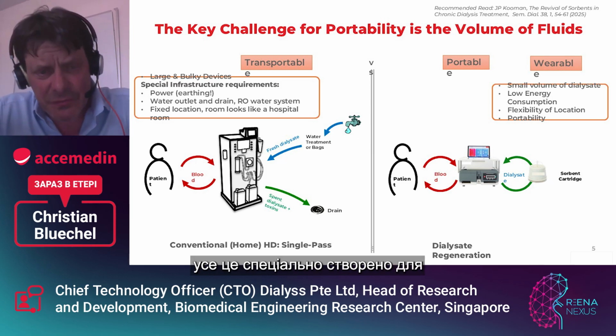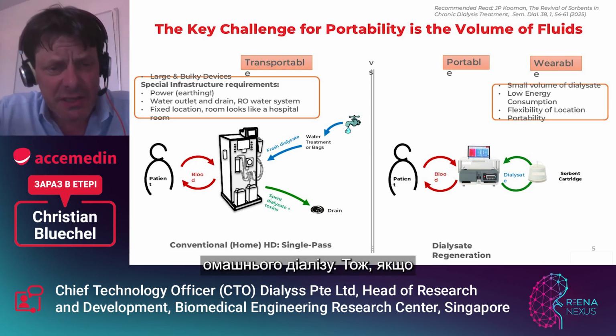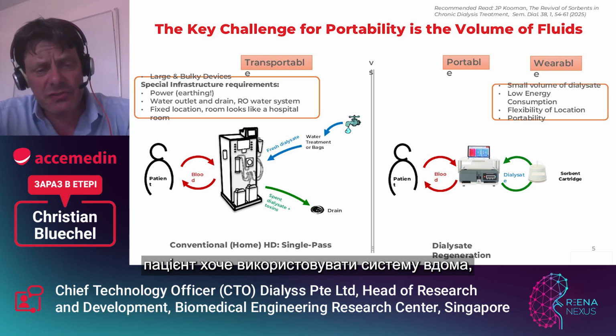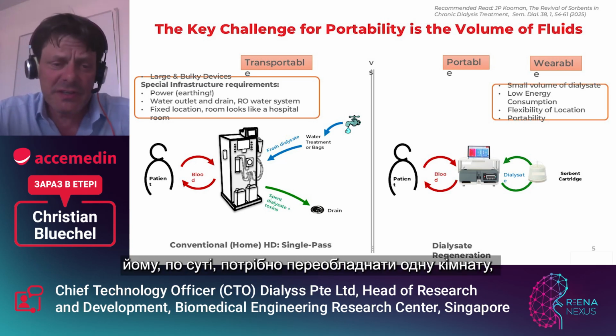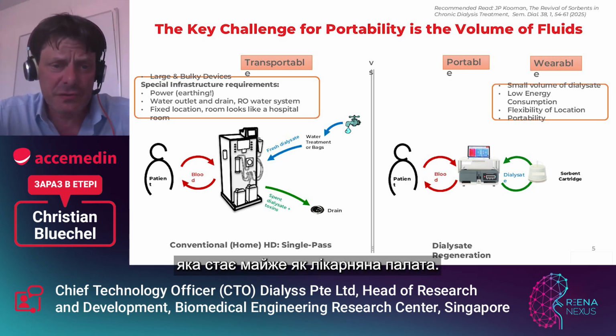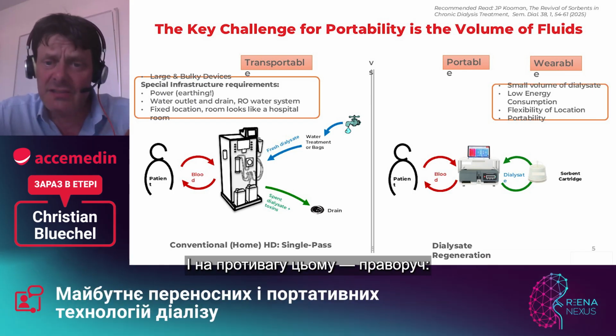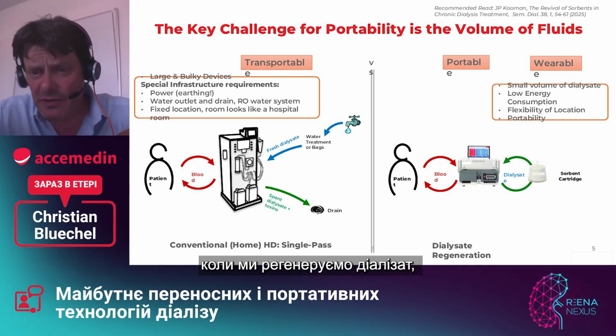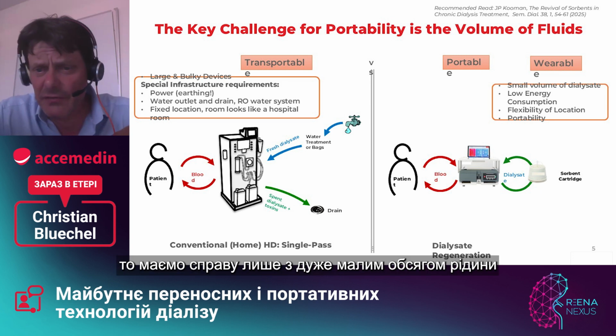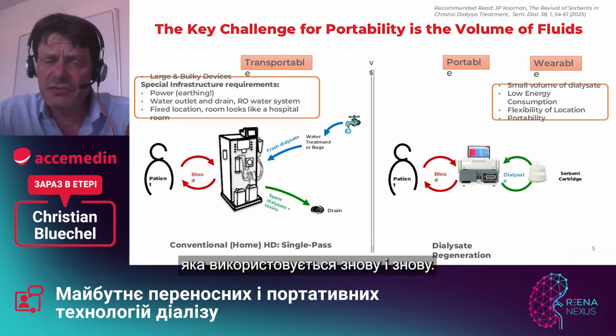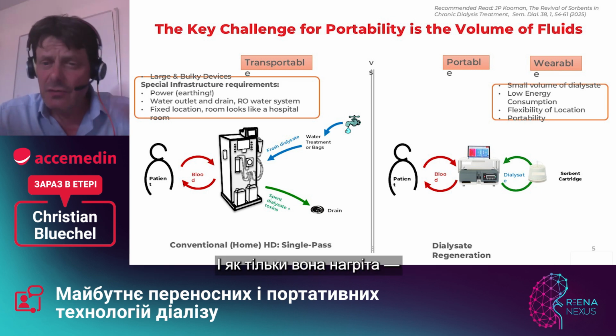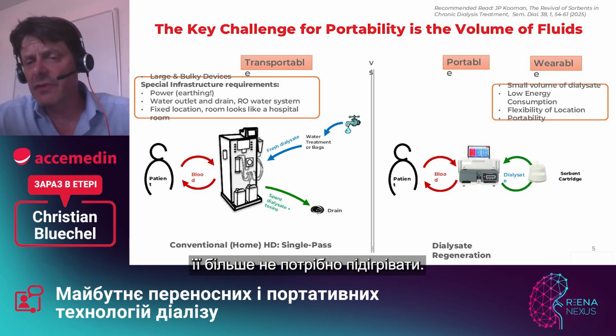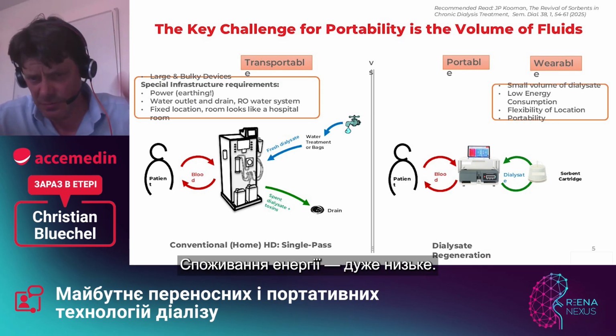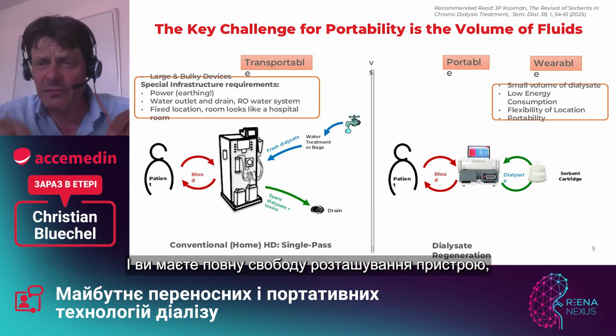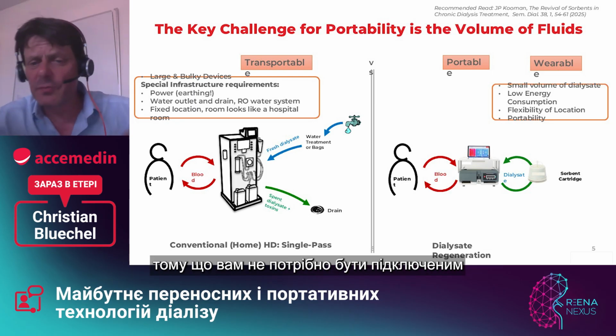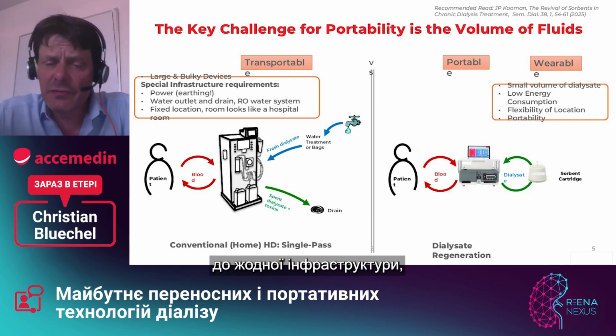This, what I wrote here, is of course specially made for home dialysis. So if a patient wants to use this at home, then basically they have to convert one room, which then almost looks like a hospital room. And in stark contrast, on the right side, when we regenerate dialysate, then you only have a very small volume of dialysate, which is used over and over again. And once it's warm, you don't need to heat it anymore. So the energy consumption is very small, and it has a complete freedom of location because you do not need to be connected to all these infrastructure things like on the left side.